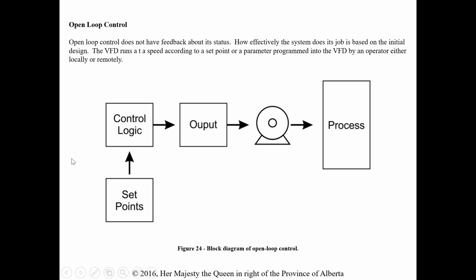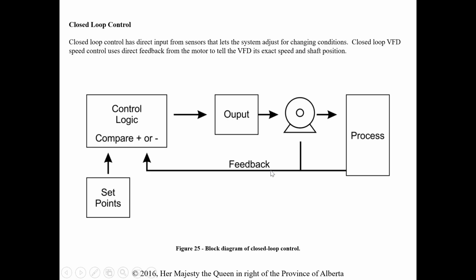Open loop control does not have feedback about its status, so we would just program it in and let it do what it needs to do. How effectively the system does its job is based on the initial programming. The VFD runs at a speed according to a set point or parameter programmed by an operator, either locally or remotely. Okay, so we set our set points, we get our output, and then we send that to our motor. That's the open loop control. So no feedback, just programmed and away she goes.